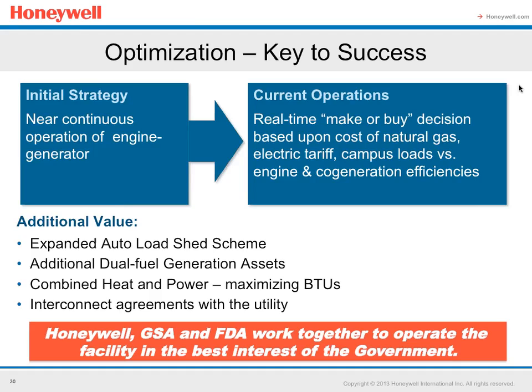Combined heat and power reduces your carbon footprint more. Typical generator sets are going to be in the 35-ish percent category for thermal efficiency. When you do CHP and actually use the steam and hot water that's produced, it goes up to 65 to 75%. So you've increased the thermal efficiency, you've wrung more BTUs out of that particular cubic foot of gas. Part of what was also referred to earlier was there's an interconnect agreement with the utility.